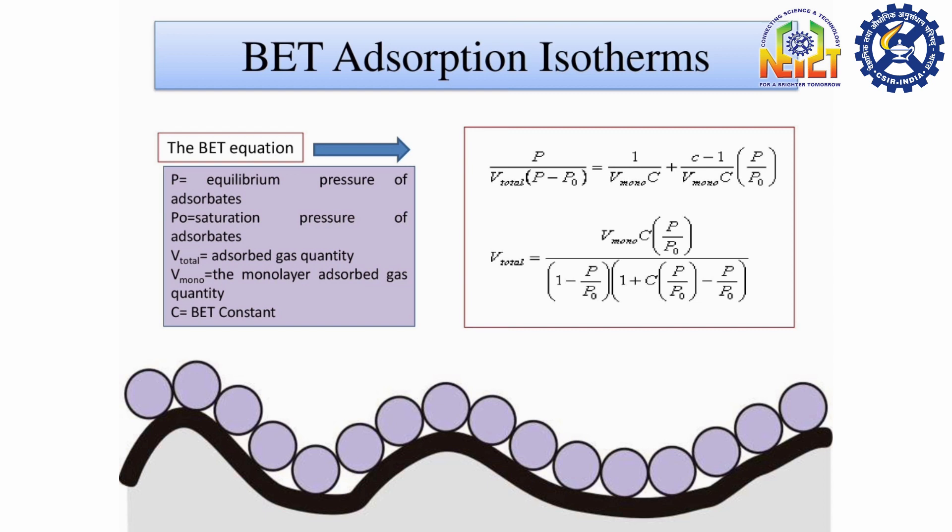Samples with low BET surface area can adequately be characterized via BET analysis by krypton gas adsorption. In those cases, only a part of the isotherm can be measured, but this still provides a BET surface area with high accuracy.